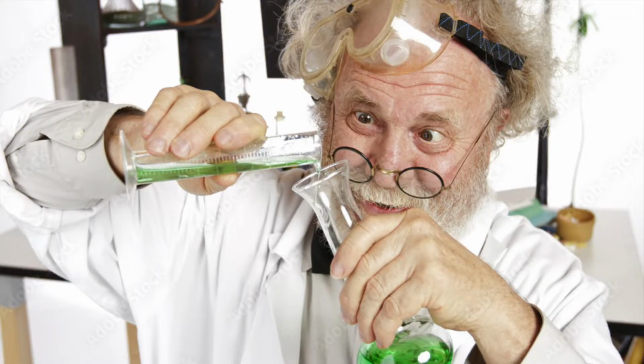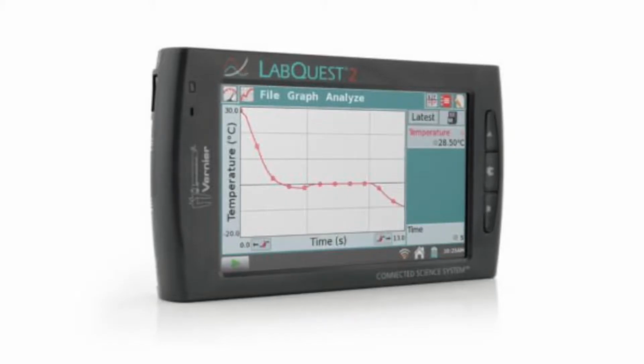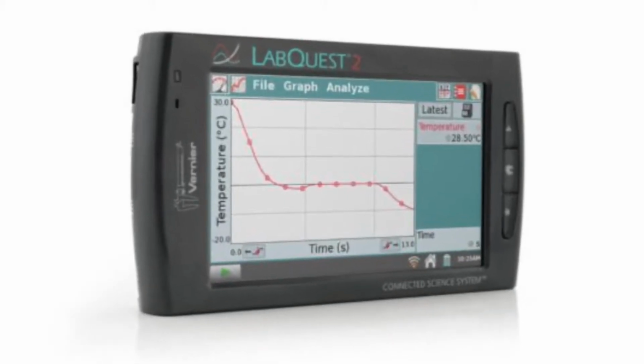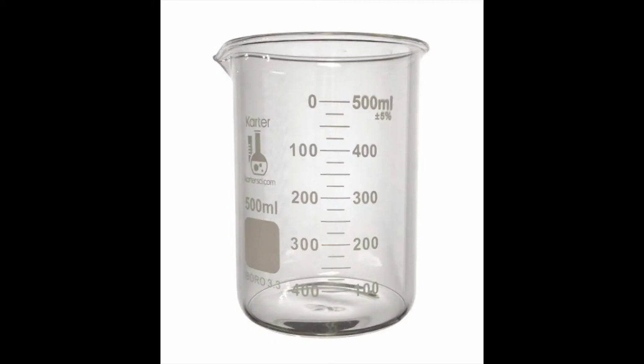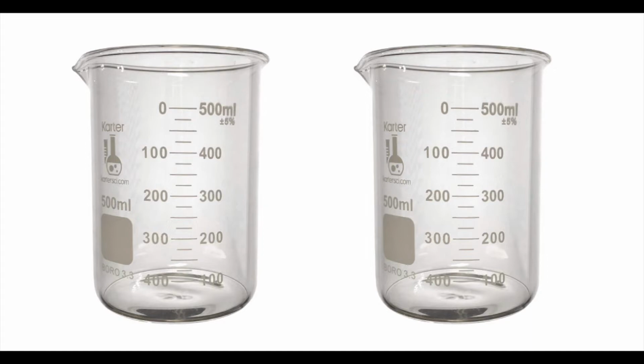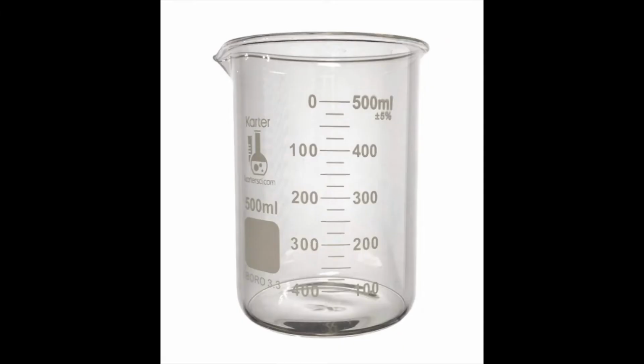So in order to start using your pH meter, you're going to need to make sure that you have a couple things ready. The first thing you'll want is obviously a pH meter. You're going to want one beaker to use for waste. You'll want 2 more beakers to fill with buffer solution. You'll need 1 more beaker filled with water to place the probe in while it is not in use. You'll want to do this to make sure that you don't damage the probe by letting it dry out.